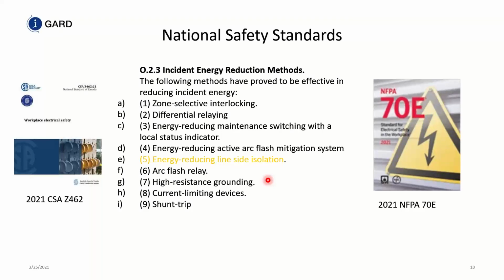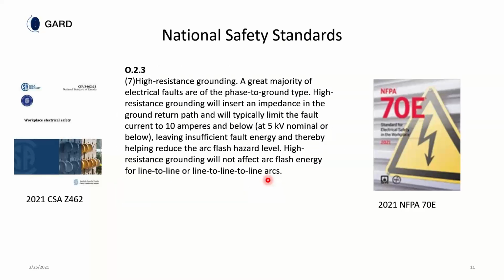High resistance grounding is the only method which prevents the probability of having an arc flash, because as the book indicated, most faults begin as single phase to ground faults and propagate to a 3-phase fault. So although high resistance grounding does not reduce incident energy, it is an arc flash mitigation technique in that it reduces the probability of having a single phase to ground fault propagate to a 3-phase fault.